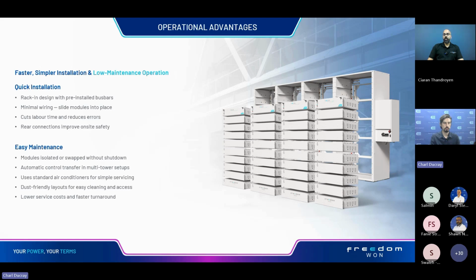Having the bus bars on the back of the rack itself keeps it away from installers, from users, from people who may be walking past, to prevent anybody from getting electrocuted and ensure the system is as safe as possible. So there are no live bus bars that can be touched by a user or operator. 100%. And we completely do away with DC cables that have to be connected at the front of the unit. So that brings us to the isolation panel.